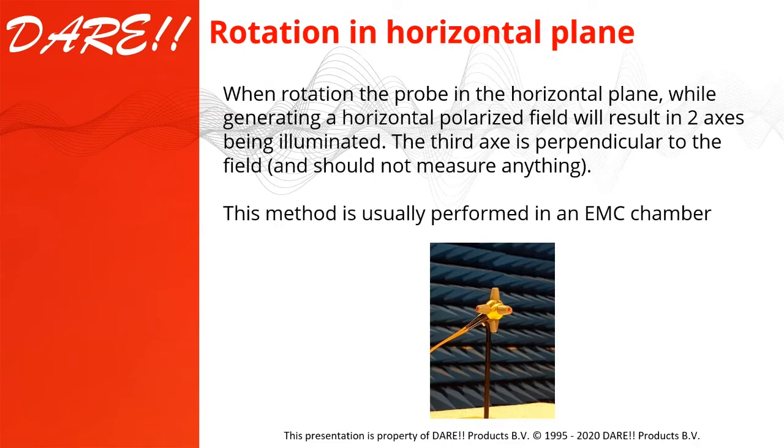This is something you can do in your own chamber, but you have to take care of the effects that can happen in the chamber. For example, the influence of objects that may reflect, for example, the table. And you might think these reflections are relatively small. Yeah, we have done quite some extensive measurements which show different. In the next webinar, we will go more deeply into this topic. So for this, I want to skip this.